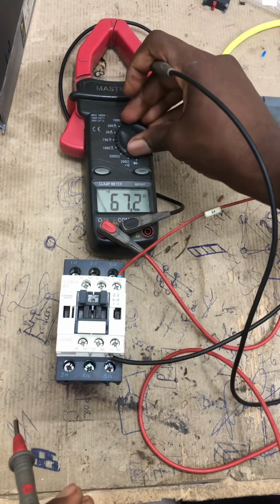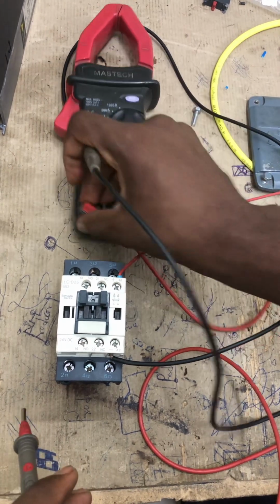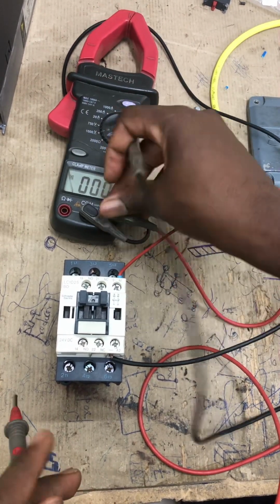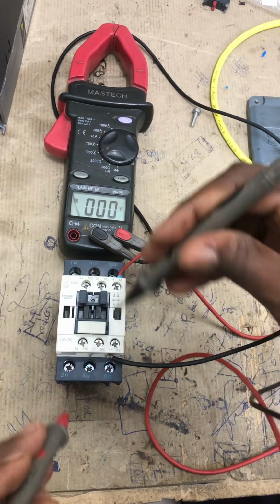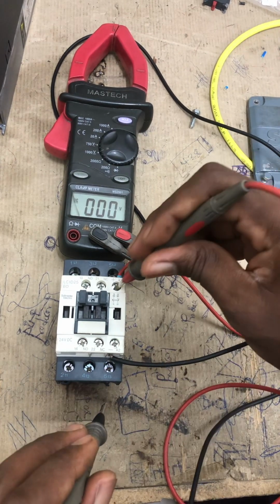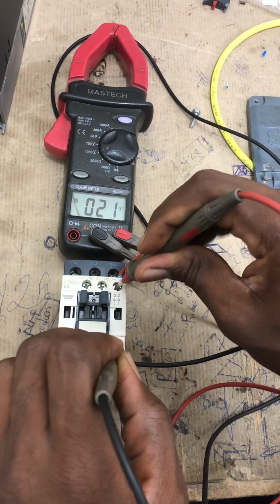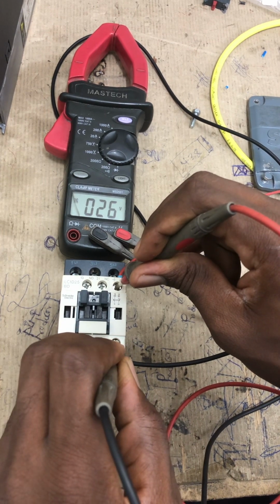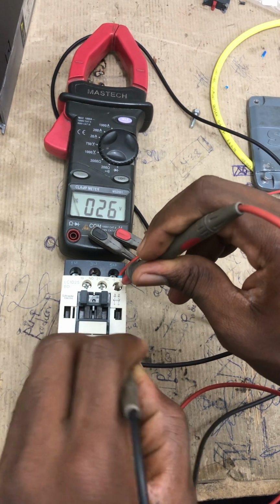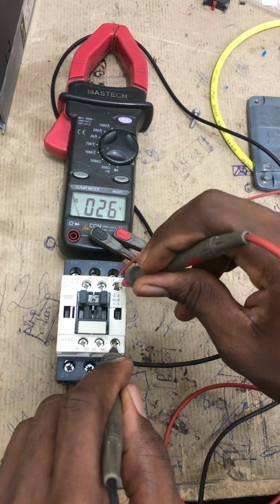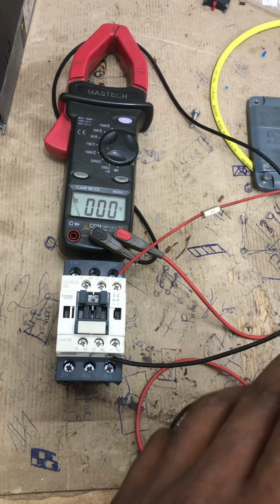And then there's the voltage across the coil, A1, A2. A1 and then A2. So you can see 25 volts, 26 volts. It's a 24 volt DC contactor. So this is how to test the functionality of a contactor.